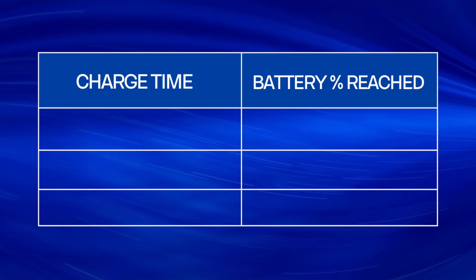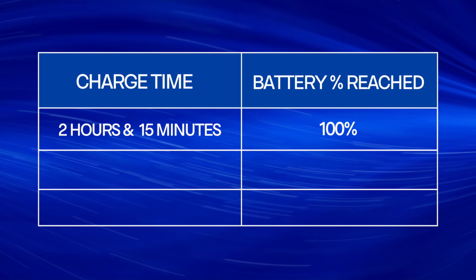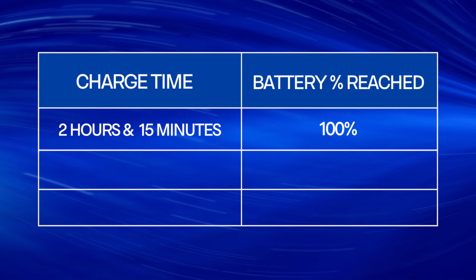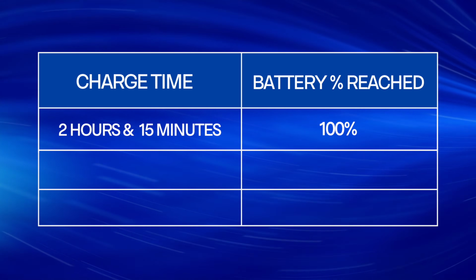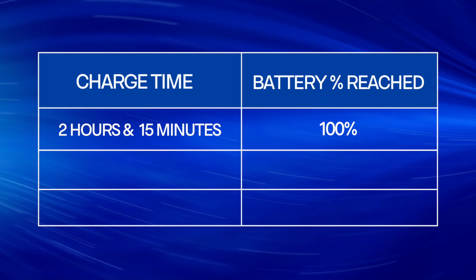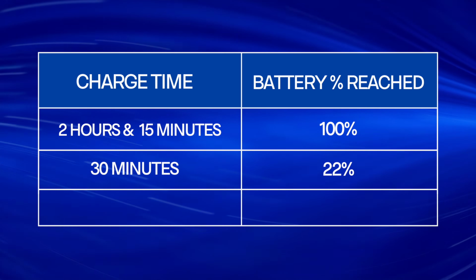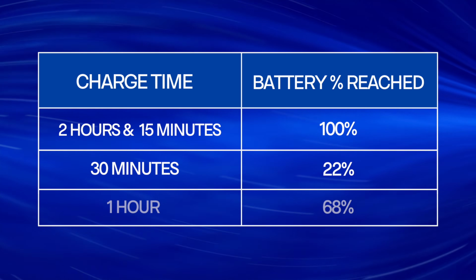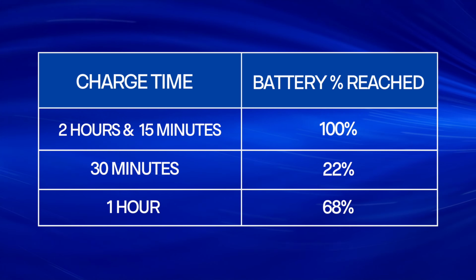Phonak also claims that it only takes 3 hours to go from a dead hearing aid up to a fully charged hearing aid, but based on my testing, I was able to go from 0% to 100% in about 2 hours and 15 minutes. Additionally, I was able to go from 0% battery life up to 22% battery life with a 30-minute charge time, and 68% battery life with a 1-hour charge time.